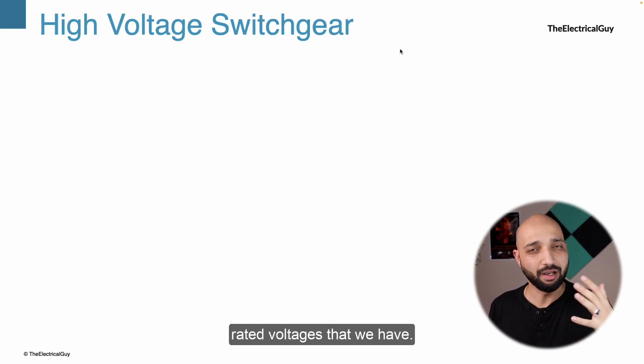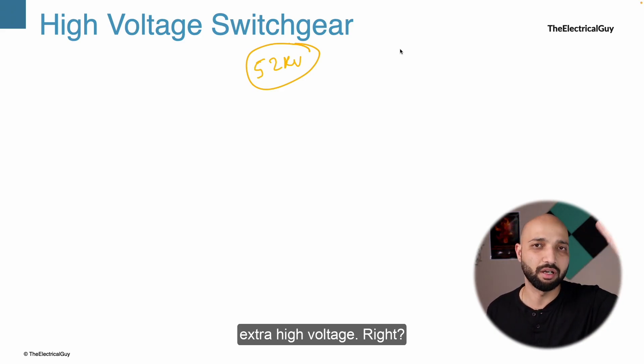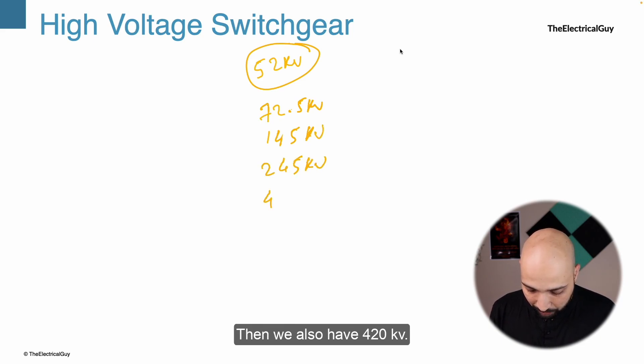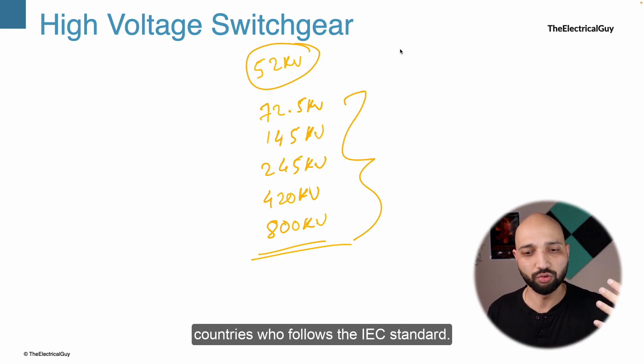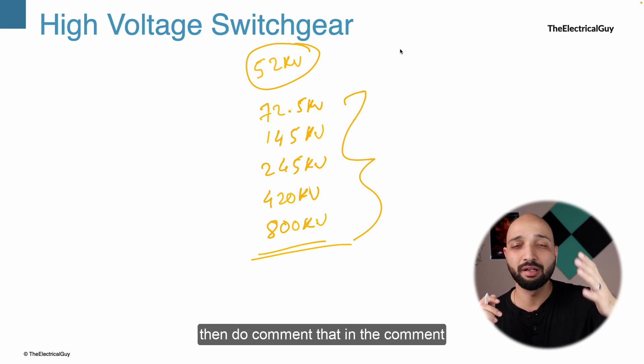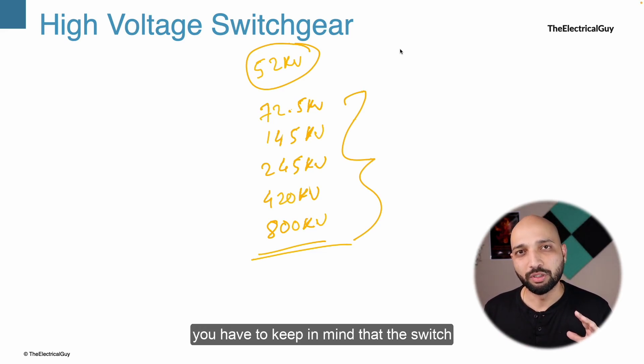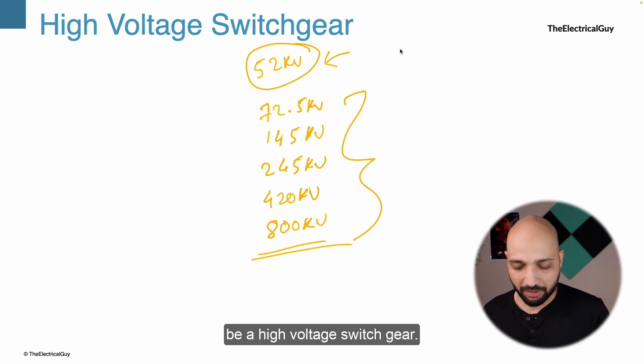Now let us see the different rated voltages. Anything above 52 kV is referred to as high voltage or extra high voltage. In India the rated voltages are 72.5 kV, 145 kV, 245 kV, 420 kV, and up to 800 kV. These are common for all countries following the IEC standard, though some may also have 550 kV. If your country has different voltages, comment below. Whenever you see these voltages, the switchgear used will be high voltage switchgear — anything above 52 kV.